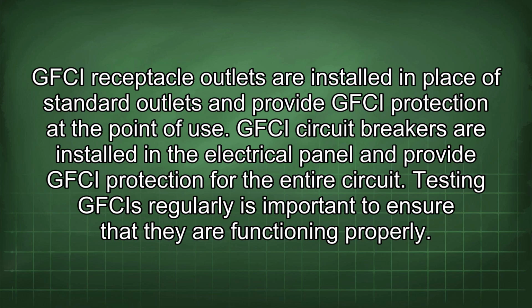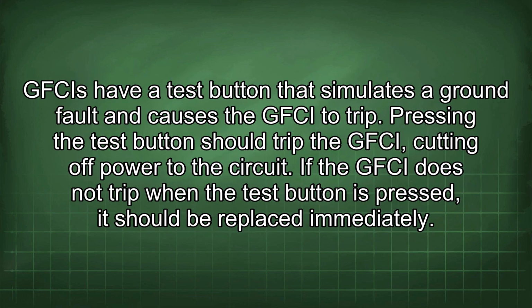GFCI receptacle outlets are installed in place of standard outlets and provide GFCI protection at the point of use. GFCI circuit breakers are installed in the electrical panel and provide GFCI protection for the entire circuit. Testing GFCIs regularly is important to ensure that they are functioning properly. GFCIs have a test button that simulates a ground fault and causes the GFCI to trip. Pressing the test button should trip the GFCI, cutting off power to the circuit. If the GFCI does not trip when the test button is pressed, it should be replaced immediately.